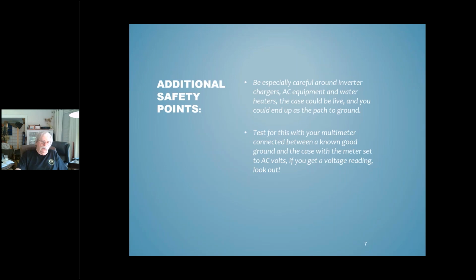It's a mild steel case, painted, but the grounding tab on it is basically a piece of sheet metal, and they do have a way of rusting out, disconnecting the ground. And if you get a short circuit in the heating element, which is not that uncommon, the case can become live, and it's a reasonably common problem.